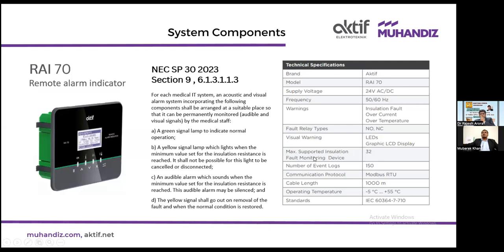There are some additional products. This particular product is a remote alarm indicator. It is recommended as per NEC SP30 2023. The requirement is that because a person cannot stay in front of the medical isolation panel continuously, there should be a device placed in a manned location where people can sit, continuously see that device, and check if there is an alarm.